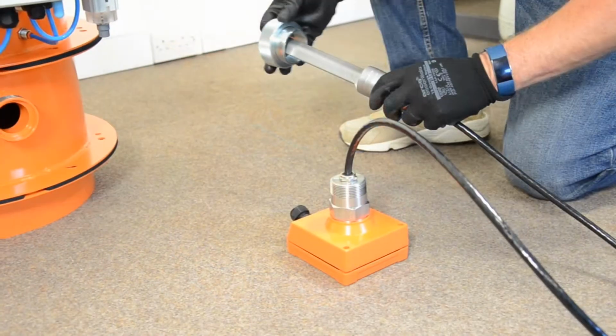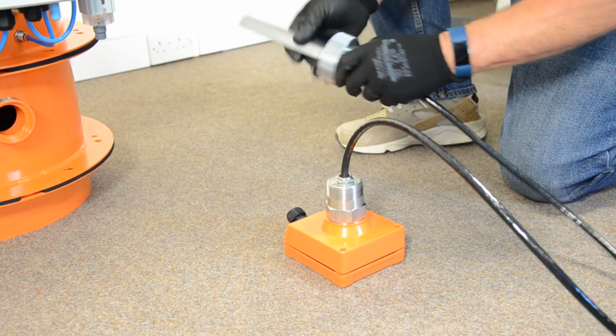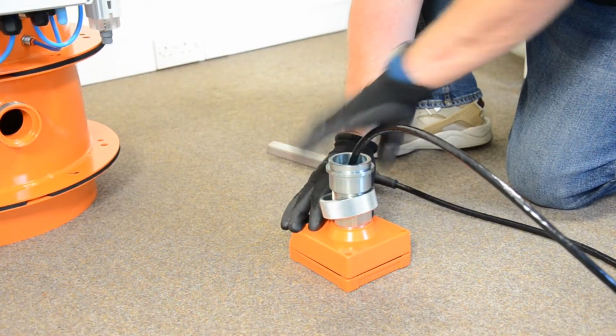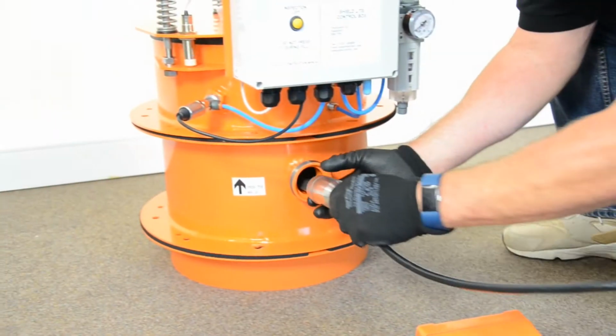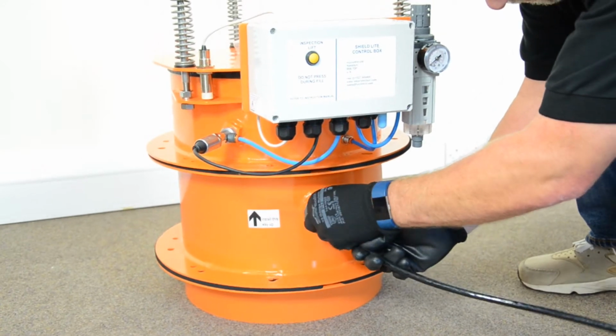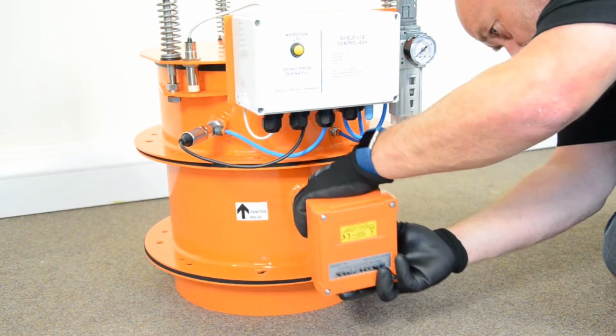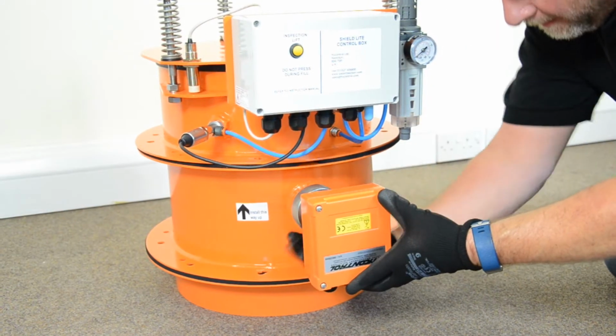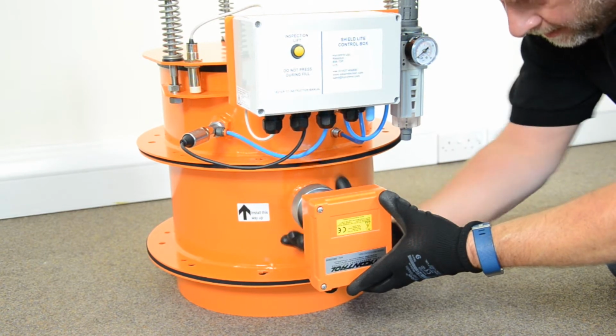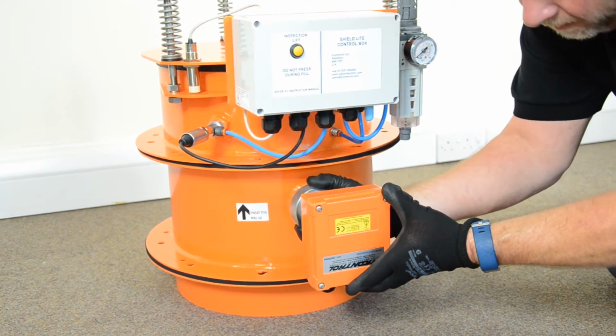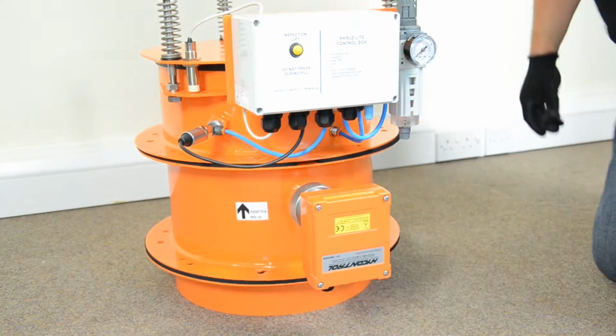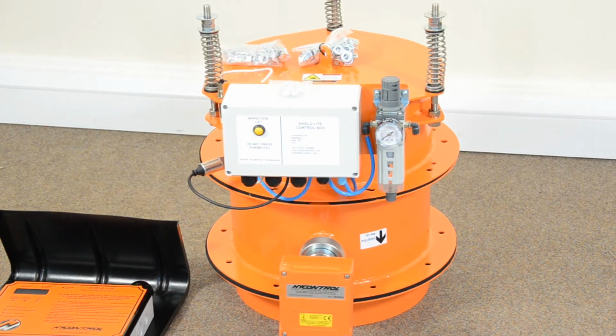The coupling is unscrewed, the probe put through, then inserted into the hole and screwed back in. It is important to make sure the probe head orientation is correct with the electrical process connection at the bottom. When everything is assembled, we can remove the covers and start wiring.